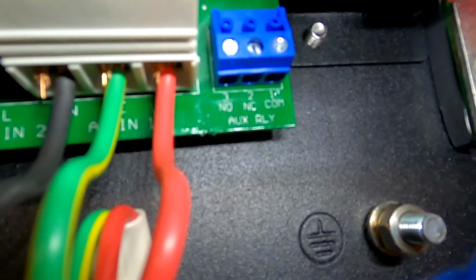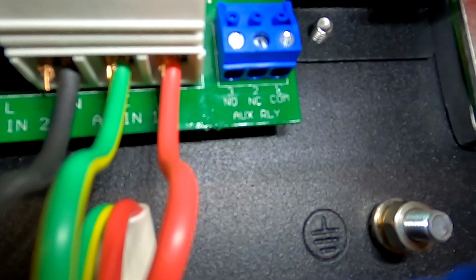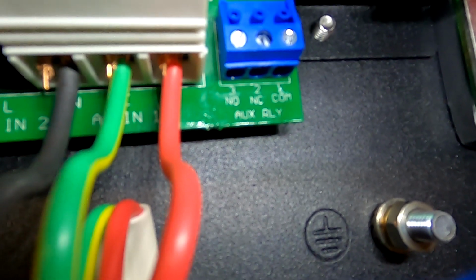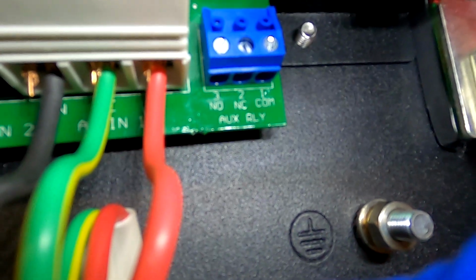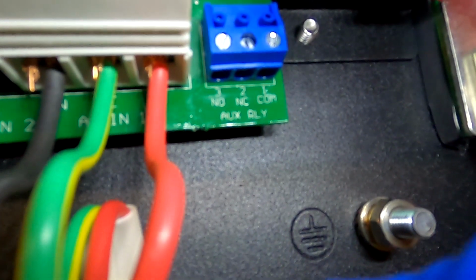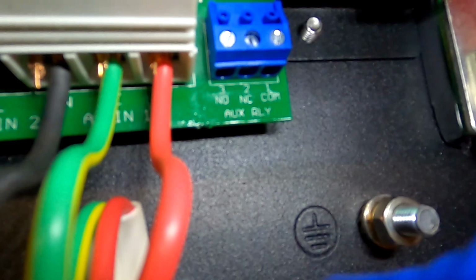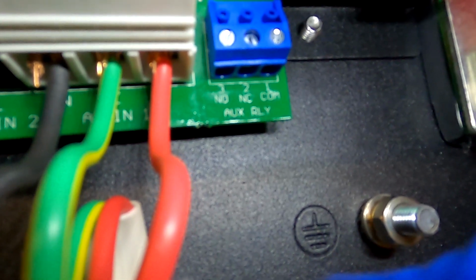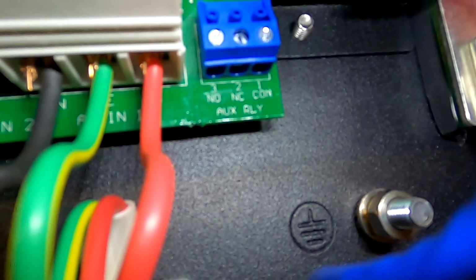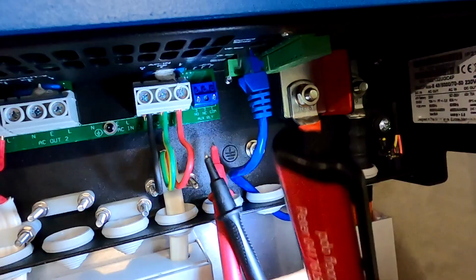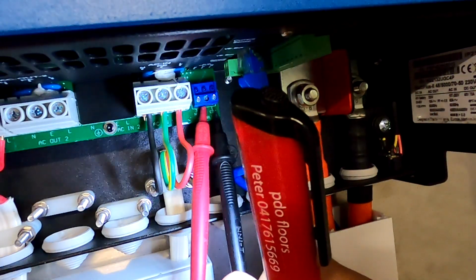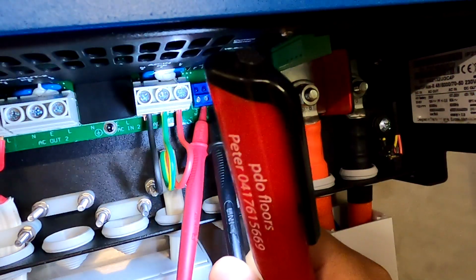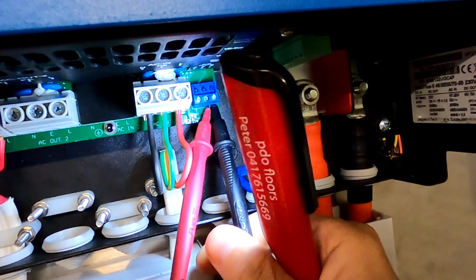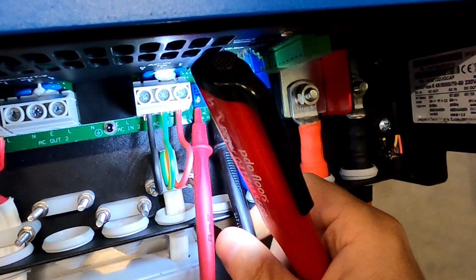So, here are the contacts of our relay in the Multiplus. We can connect our cables to the NO, NC and COM terminals of the relay. Because the relay is not programmed at the moment, we should have continuity between the COM port and NC, which is a normally closed contact. So we should have continuity. Yep, there we go. And the other one is not connected.